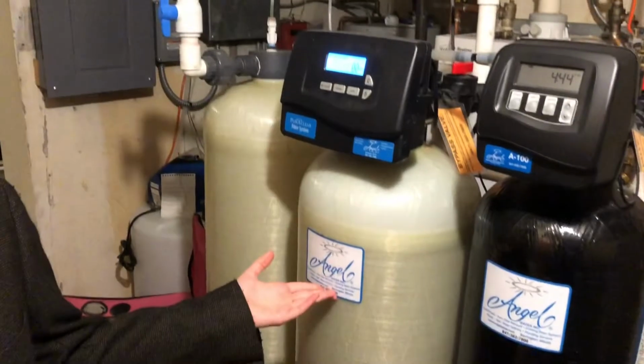Now we will move on to the treatment portion of the treatment train. The first step in the treatment train is coagulation. This removes turbidity, color, and some bacteria from the water. This is done by adding coagulants, such as aluminum sulfate or ferric chloride, to neutralize the particles in the water. This causes them to clump together and form something called a floc.